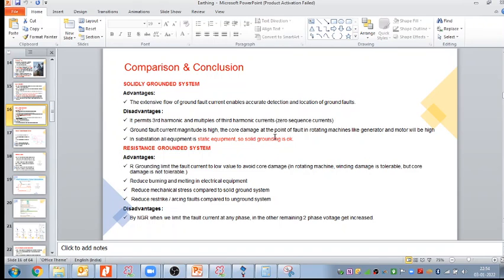The core damage at the point of fault in rotating machines like generator and motor will be high due to the high fault current. In a substation, all the equipment is static equipment, so solid grounding is okay for the substation. Right? That covers the advantage and disadvantage of the solid grounding system. Now the resistor grounding system advantage: resistance grounding limits the fault current to avoid core damage. In rotating machines, winding damage is tolerable, but core damage is not tolerable.